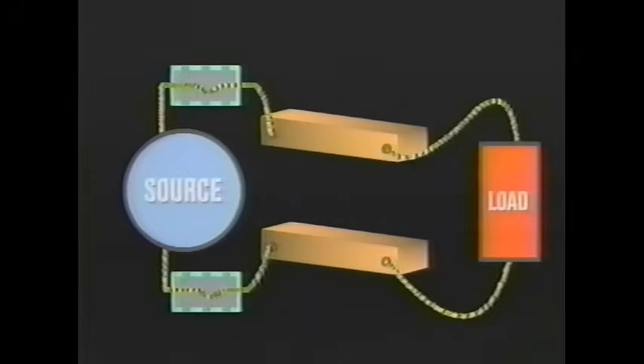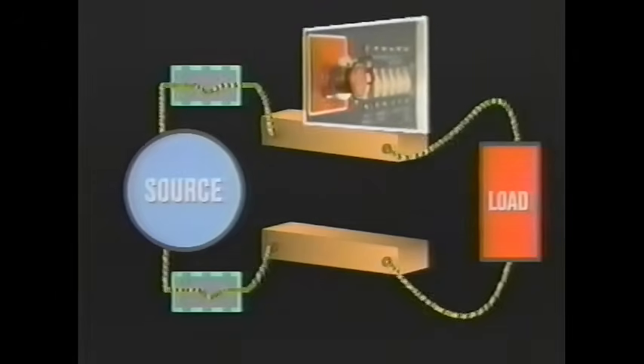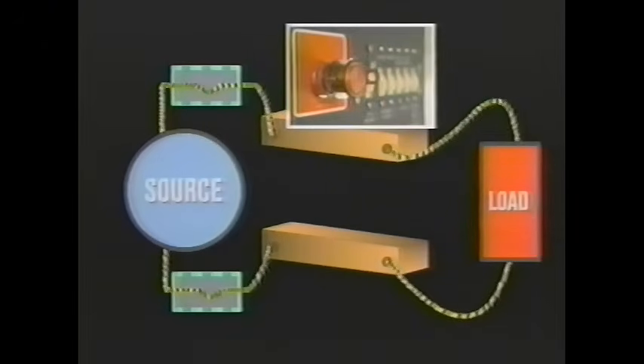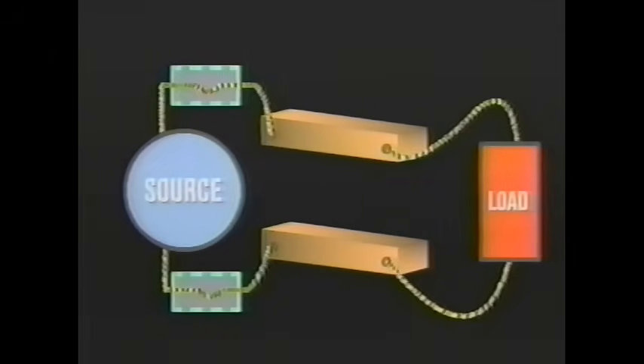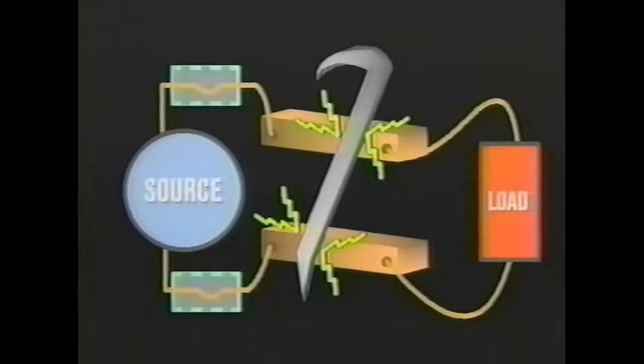The third system will discharge the capacitors whenever the diesel engine shuts down. When the diesel engine shuts down, the auxiliary generator ceases to produce output. The inverters require auxiliary generator output to function properly. So when auxiliary generator output is lost, the inverter triggers a protective electrical crowbar. This electrical crowbar creates what is essentially a direct short circuit across the capacitors, which discharges them instantly.